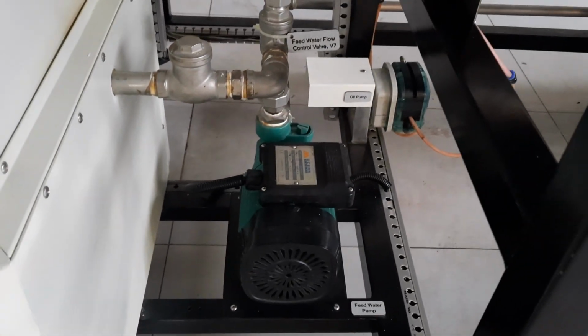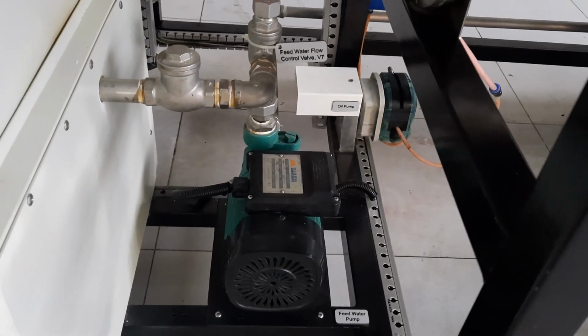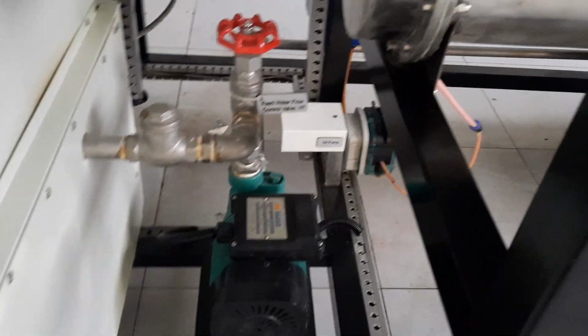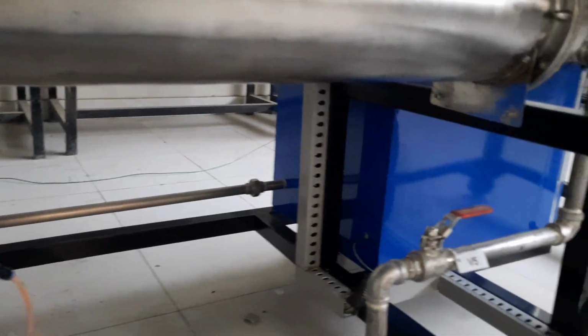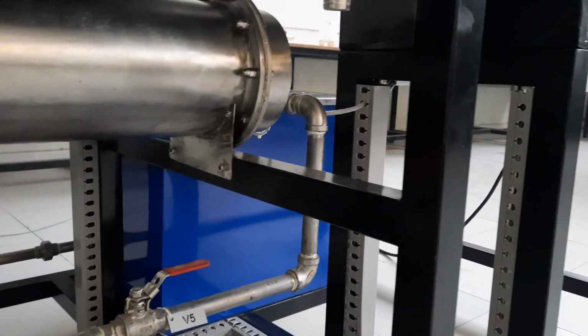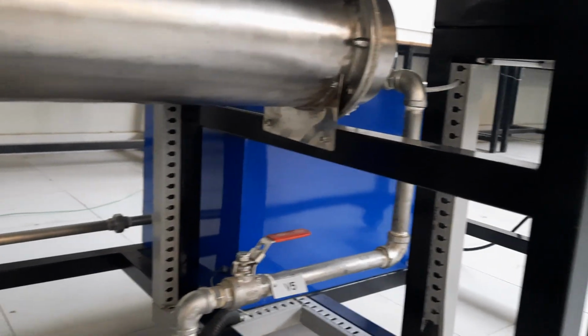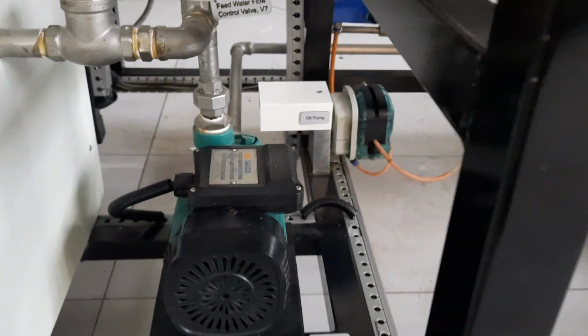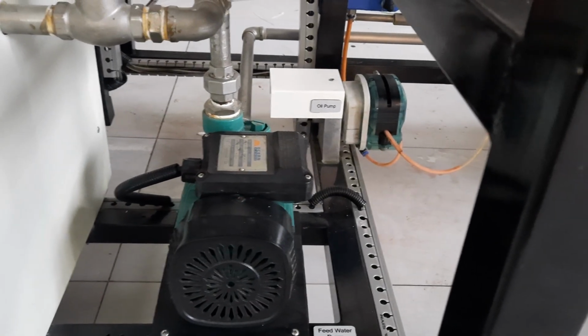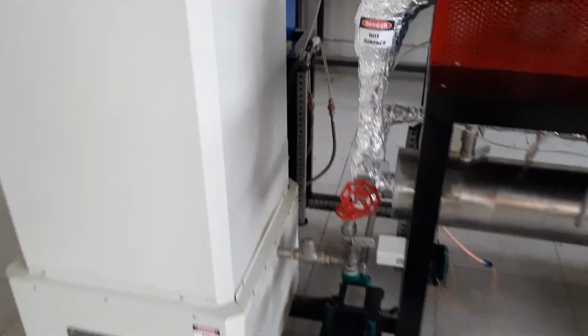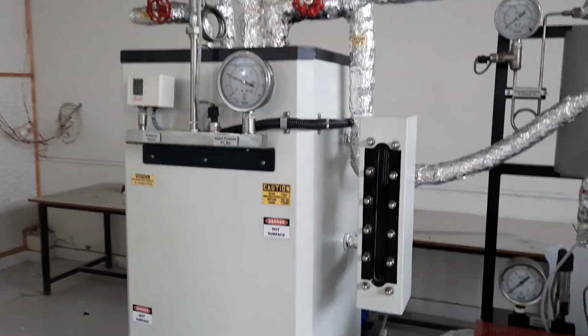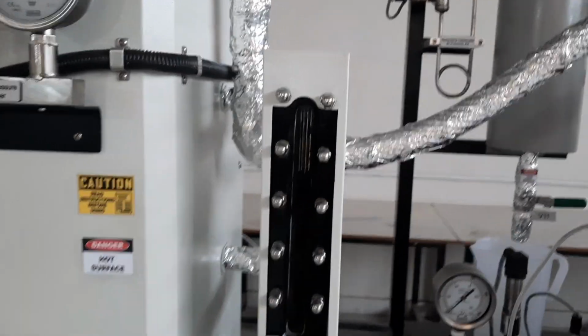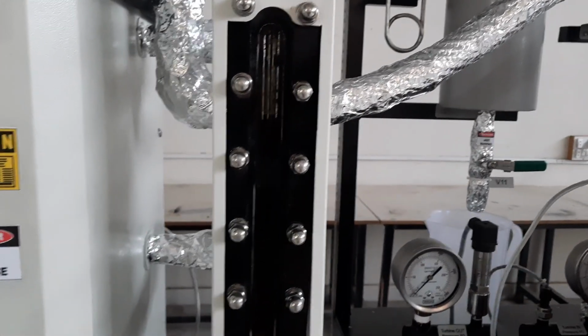This is the feed water pump which takes water from the feed tank. This large blue tank at the back is the feed water tank. This pump takes the water from the feed tank and fills this boiler. Water level in the boiler can be shown in this sight glass.